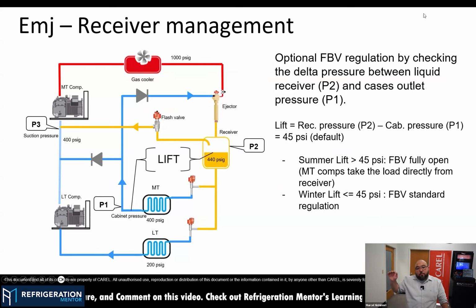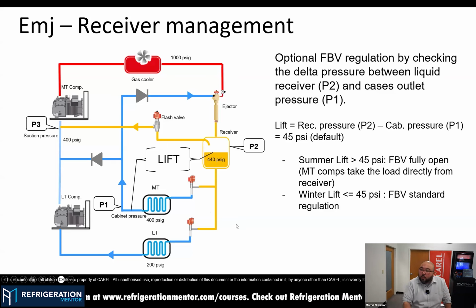And during winter, what we would do is change the logic of the high pressure valve, the flash gas bypass valve, and control it to maintain the pressure on the liquid receiver. So to maintain the minimum delta that we need to cover the pressure drop on the expansion valves here, both MT and LT. Mainly MT, since on LT we have a bigger pressure delta. So the receiver management will be with a dynamic set point, and we calculate this based on the pressure here. So we will try to maintain a lift here, always to maintain a pressure delta that would make an increase in pressure based on this pressure here. So it will be floating based on the case cabinet pressure. Does it make sense?